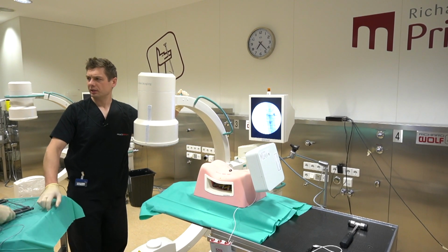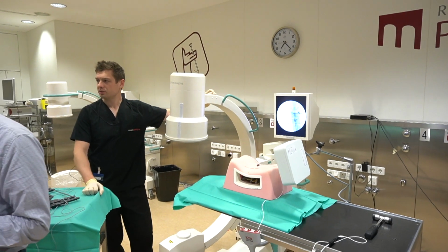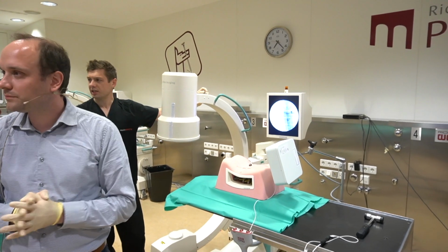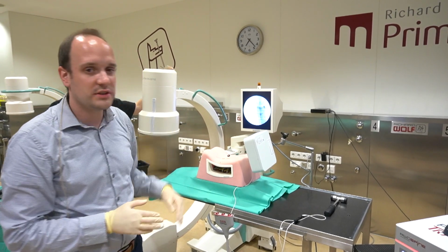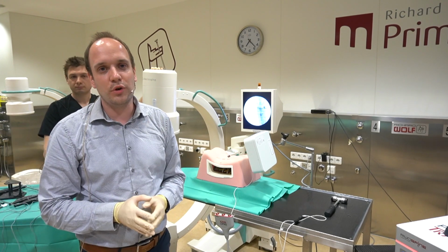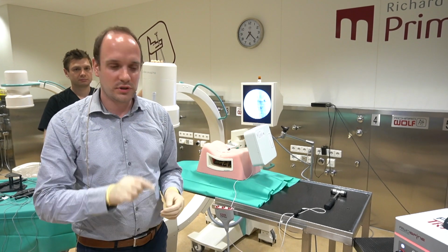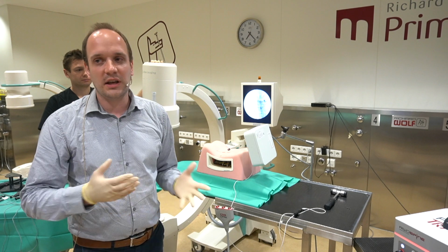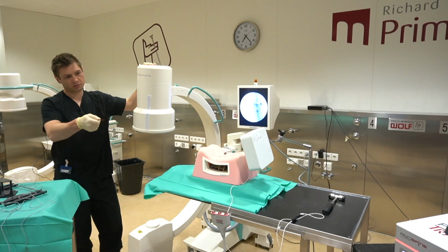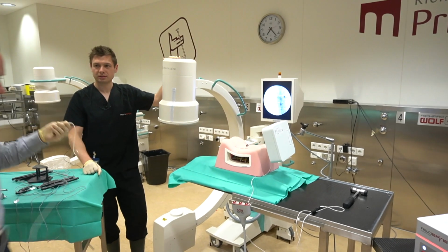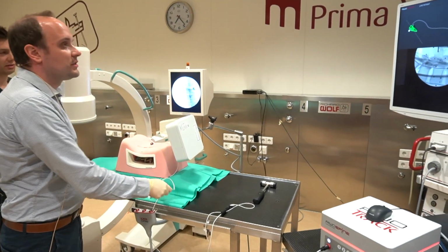There is a question, Frederick. Maybe lateral and AP, we take the picture by USB stick, I think, and insert in the navigation. So in this case, we transfer the image with a USB stick because our C-arm here is not capable of a DICOM push. But with a modern C-arm, there will be a DICOM push. That means on the C-arm, you click the button, send to RIWOtrack, and RIWOtrack will receive the image. Yeah, and if you have an older version as we have, you need to do this manually by USB stick, but it also works. Usually, if it's not older than 15 years, it works directly.